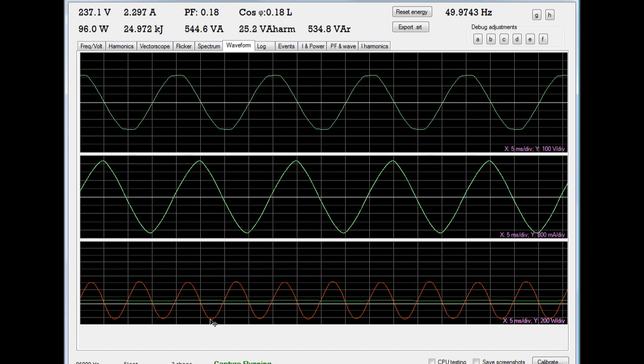Well, positive watts mean energy being transferred from the grid into the load. In the case of my incandescent lamps, energy was being transferred from the grid into the filament. So negative power means energy is being transferred from my light back into the grid. So what in effect is happening is the lamp ballast, the magnetic ballast, is taking more power than it needs, storing it, then going, oh, oops, I've taken too much energy, and dumping it back into the grid over the next half cycle. So you have a lot of amps shuffling energy backwards and forwards in and out of the ballast and back in and out of the grid.